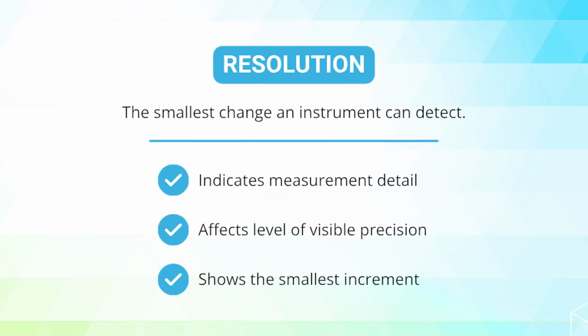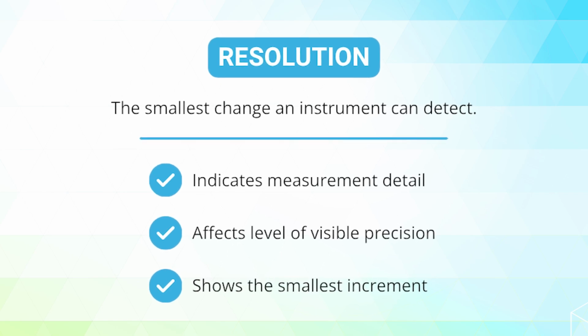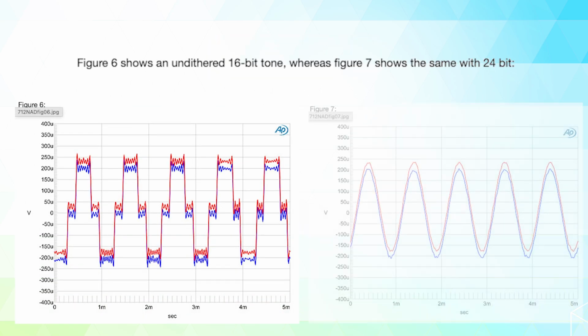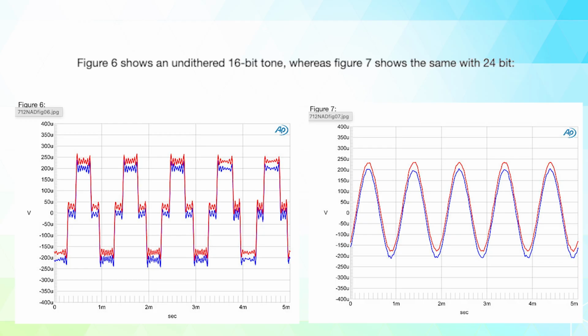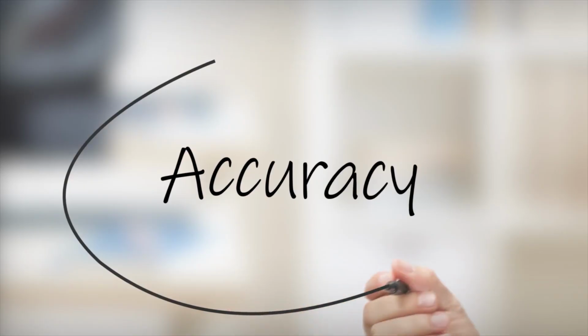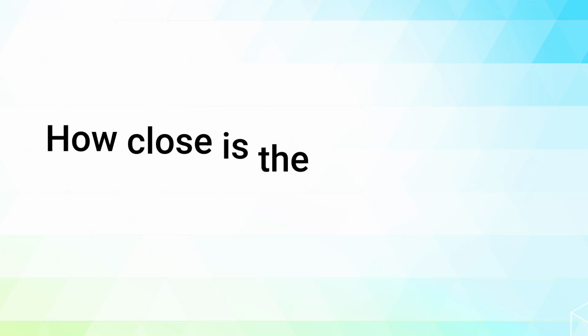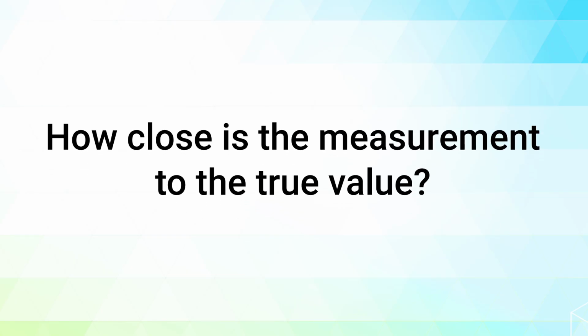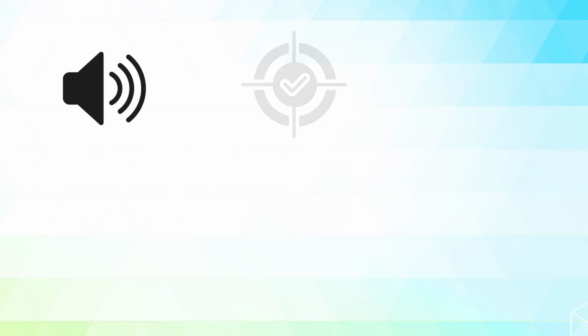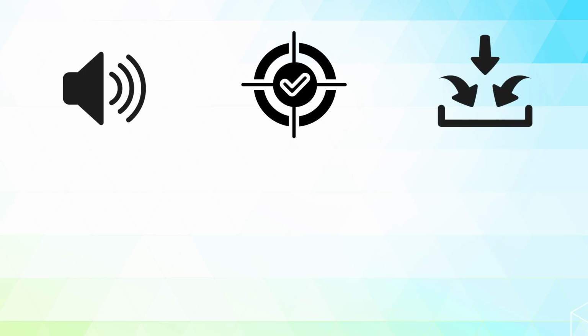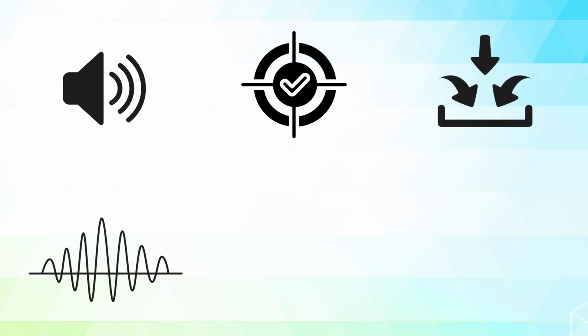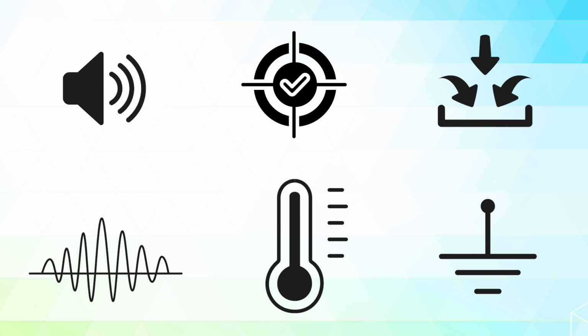Resolution tells you how finely a device can divide a measurement range. For example, a 16-bit device divides its selected range into thousands of tiny steps, while a 24-bit device divides that range into even smaller steps. That can be useful, especially when you need to see small changes in a signal. But accuracy answers a different question. How close is the measurement to the true value? A system can have high resolution and still be inaccurate if noise, calibration drift, poor input range selection, incorrect signal conditioning, temperature changes, or grounding problems are affecting the signal.